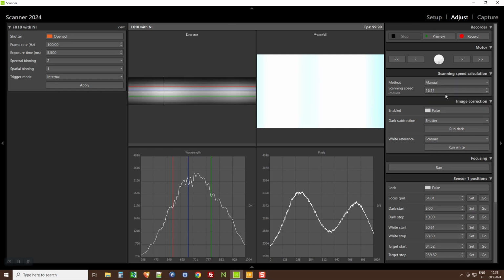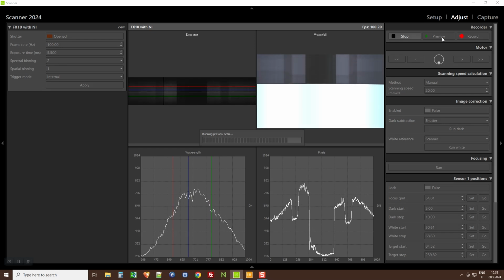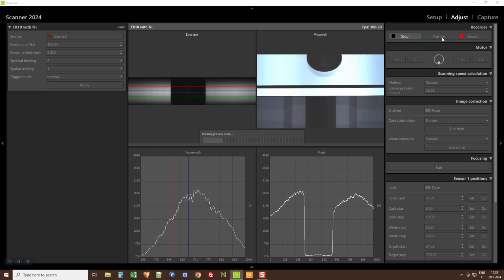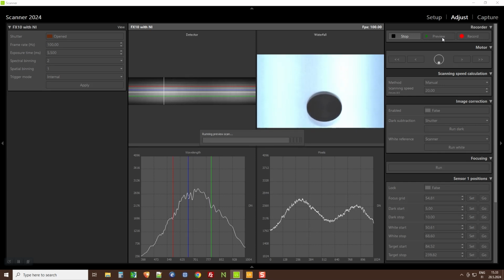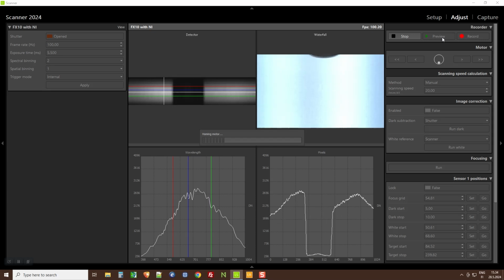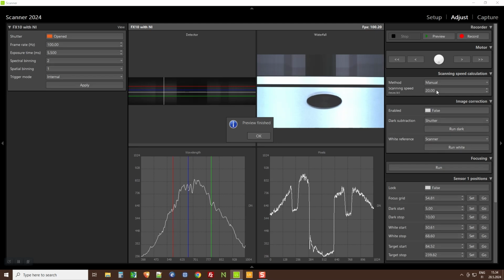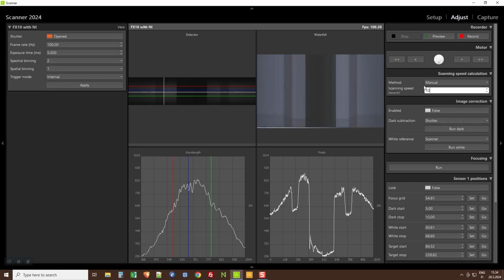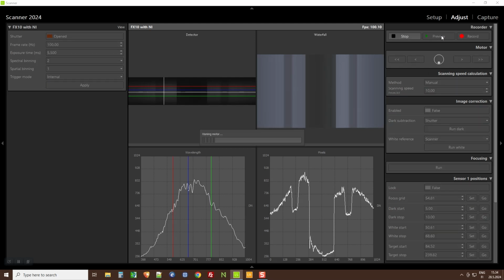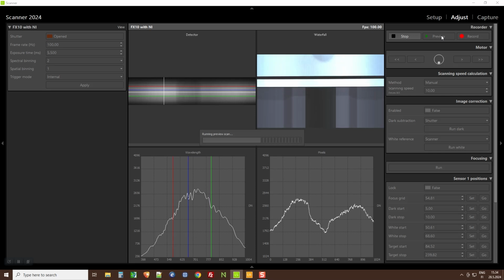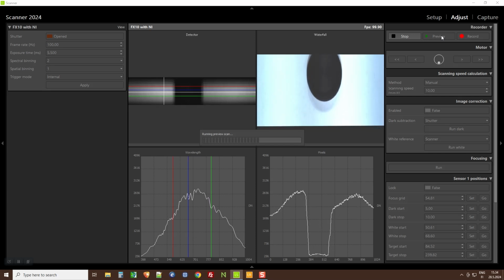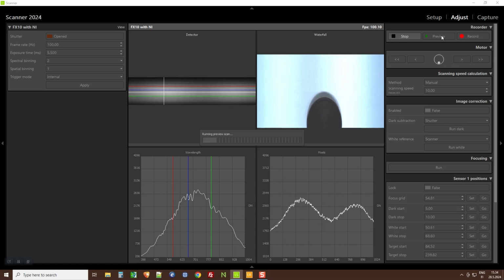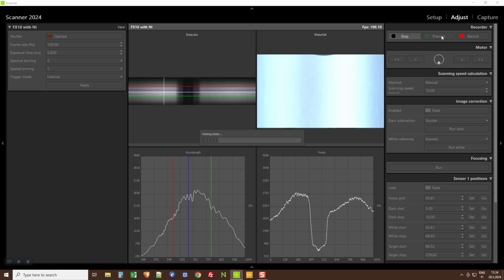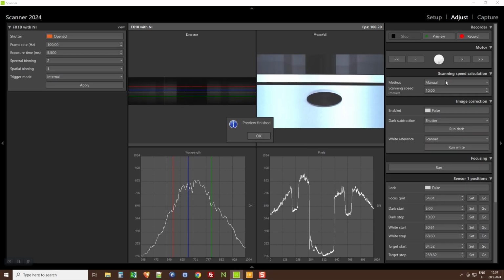First, I will adjust it manually. For example, what happens if I move at 20 millimeters per second? We will see if the round object will appear as round. So here we can see that the scanning speed is a little bit too fast because the round is not round anymore, it shrunk. If I put something which is too slow, it will be looking like an egg. So for example, if I put this time 10 millimeters per second and we make a preview, we will have a very elongated object like this. So in some application, you would like to do that so that in terms of pre-processing, after you have acquired the data, you can make like this a merging of data together. So you can compute like average frame, like shrinking things together. Typically, we do not do it, but you have this possibility.